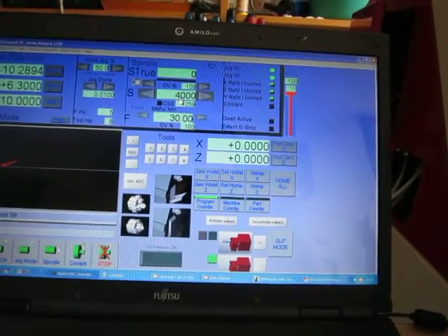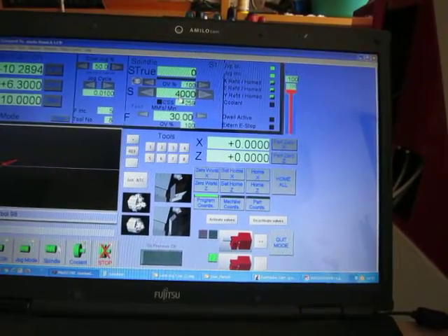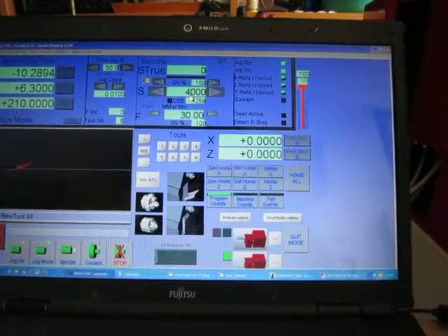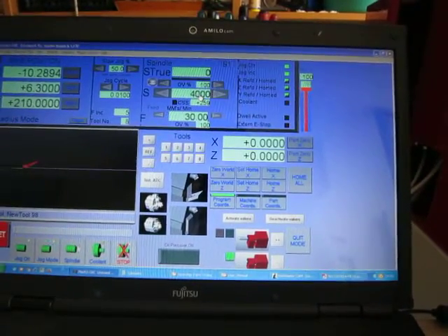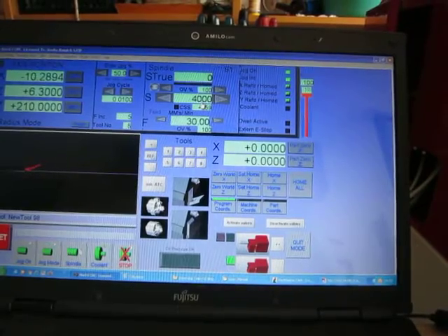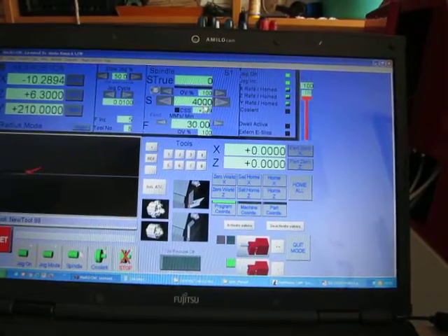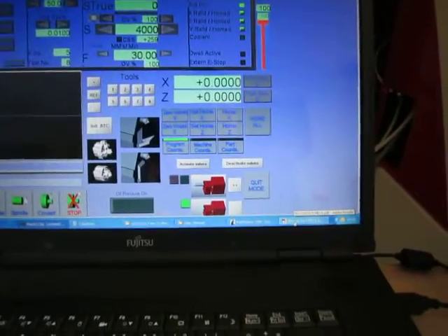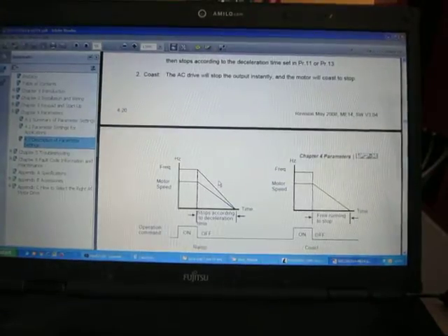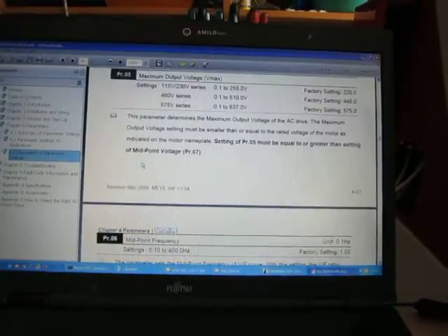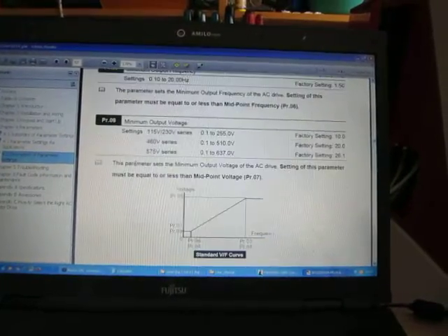Of course, it's normal to take a little bit more time to accelerate to 4000 RPM than to 3000 RPM, but the difference of about 1000 RPM was so big. So I went to read the manual for what each parameter is, and parameter 10 is for setting acceleration time.